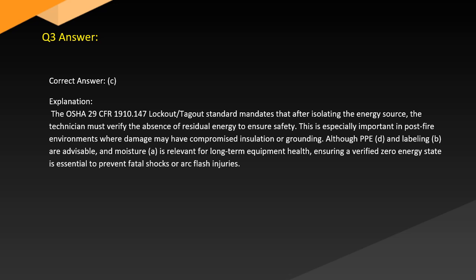Answer. Correct answer: C. Explanation. The OSHA 29 CFR 1910.147 lockout standard mandates that after isolating the energy source, the technician must verify the absence of residual energy to ensure safety. This is especially important in post-fire environments where damage may have compromised insulation or grounding. Although PPE (D) and labeling (B) are advisable, and moisture (A) is for long-term equipment health, ensuring a verified zero energy state is essential to prevent fatal shocks or arc flash injuries.